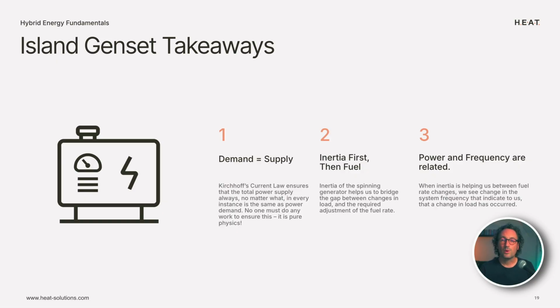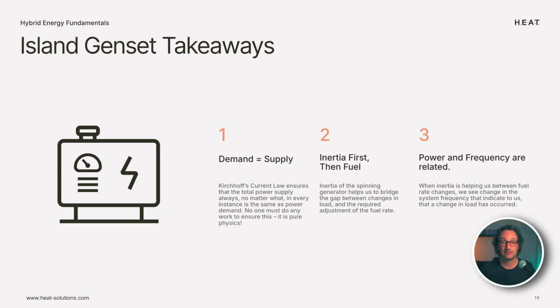And that's it. What I want you to take away from this lesson is that, number one, demand always equals supply. Kirchhoff's current law ensures that the total power supply always, no matter what, in every single instance is the exact same as the power demand. Nobody has to work to ensure this. It's just true. Number two, this is achieved through the use of inertia first and then fuel. Inertia supplies changes in load, and then the fuel rate is adjusted afterwards. And number three, power and frequency are related.